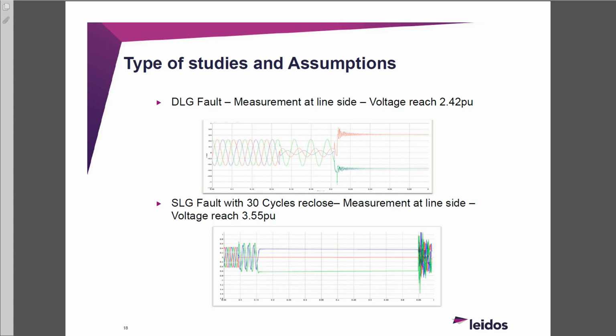That's a whole other conversation, but go ahead, continue. So in this one, as you see, I have a single line to ground with a high speed reclose of 30 cycles, and my TOV goes to 3.5, and that makes sense, right? Because the line is still energized. So you close the line, it's still energized, so your voltage goes way higher. So you have trap charges. Exactly, you have trapped charge, you didn't give enough time to discharge.